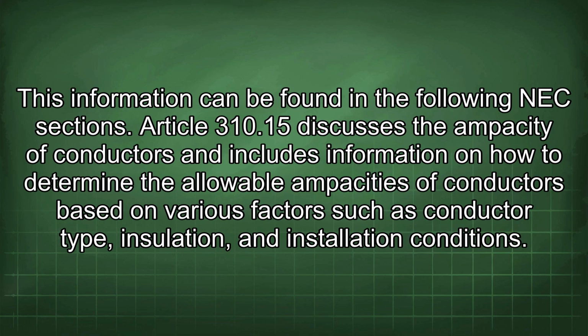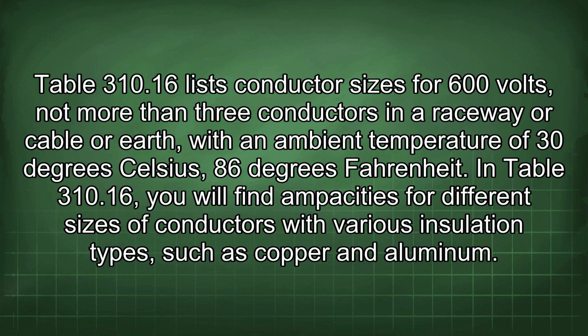This information can be found in the following NEC sections. Article 310.15 discusses the ampacity of conductors and includes information on how to determine the allowable ampacities of conductors based on various factors such as conductor type, insulation, and installation conditions. Table 310.16 lists conductor sizes for 600 volts, not more than 3 conductors in a raceway, cable, or earth, with an ambient temperature of 30 degrees Celsius, 86 degrees Fahrenheit.